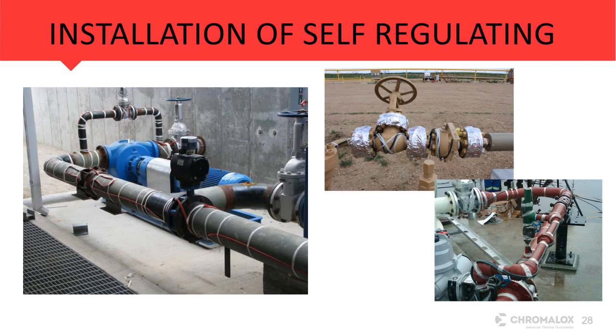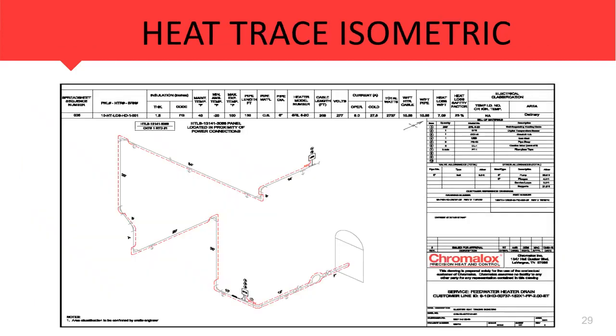One of the things that I like to do if we're going to do some testing or troubleshooting on heat tracing is to start with a basic heat tracing isometric. That isometric is going to give us the maintained temperature. It'll give us the pipe length. It'll give us the circuit length of the heat tracing. It'll tell us what our startup amps are, what our steady state amps are. So it's just a great starting point for going out and troubleshooting.